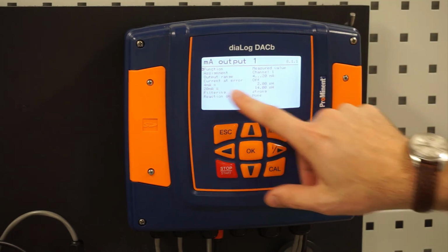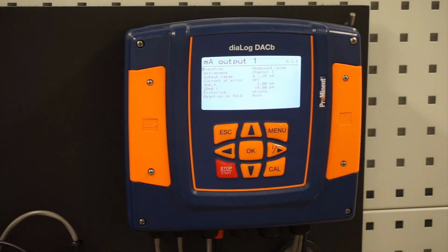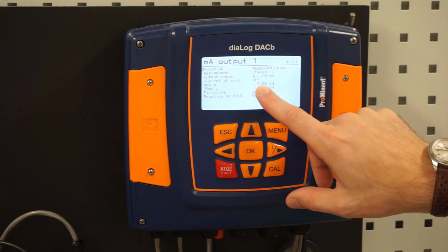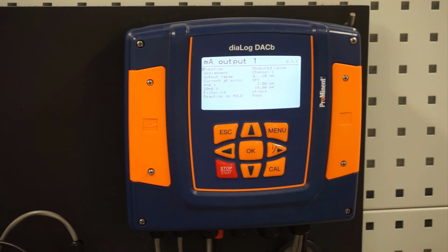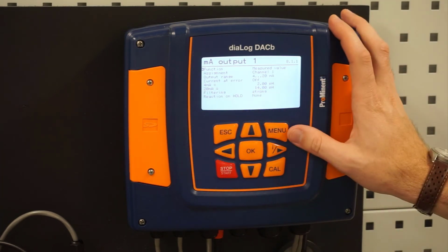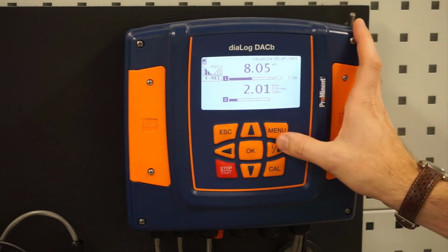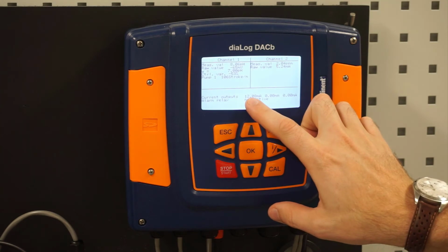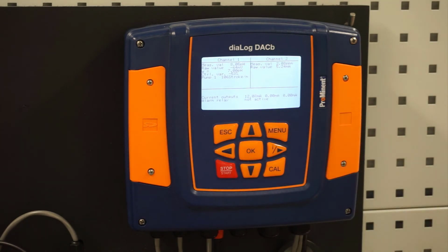And you have to set your range depending on what they are looking for back in the control room so that they match up. So right now 4 milliamps is going to give us 2, and 20 milliamps is going to give us 14 pH. So if I back all the way out, we are currently at a pH of 8.06. So if I come down here, that represents 12.0 milliamps. I can send that out to the customer and they could data log it. They could just display it on their screen to see what it is, or they could take that value and then control from their control room.